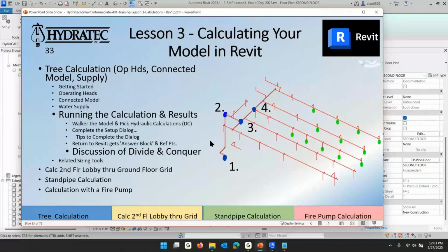But by testing it there, I'm saying you could figure out where the problem is down to like 3 pipes in about 4 tries. And if you say the problem's between here and here, almost always you say, oh, that's it. I forgot. I used arm over pipe for the main or something. But very, very powerful tool. And Mike Kulik and I came up with the idea of labeling it divide and conquer, but we think Julius Caesar came up with the concept.